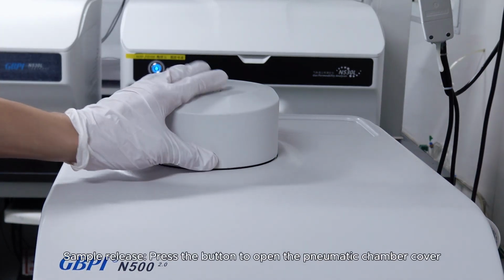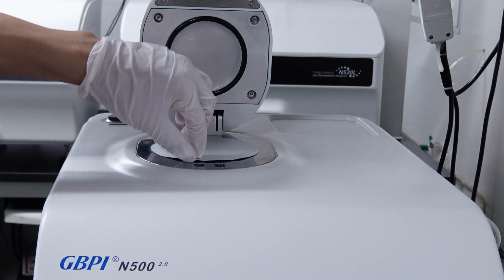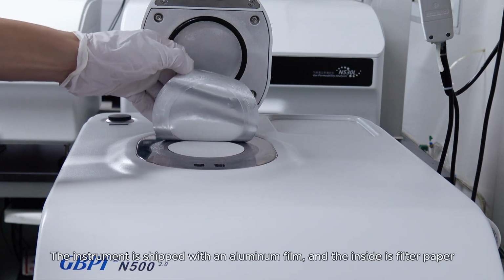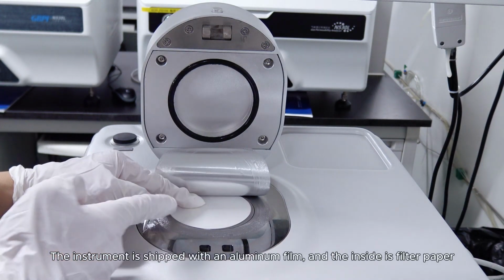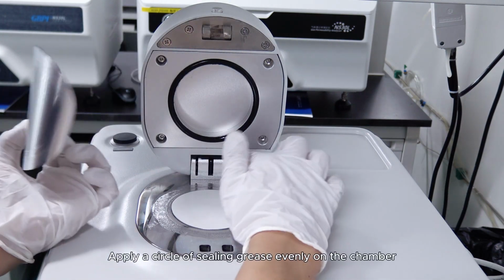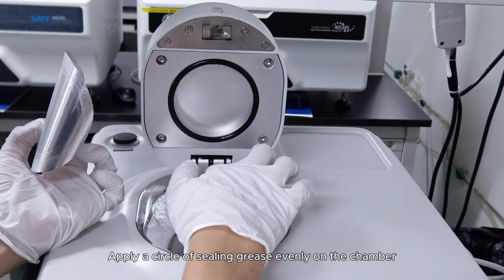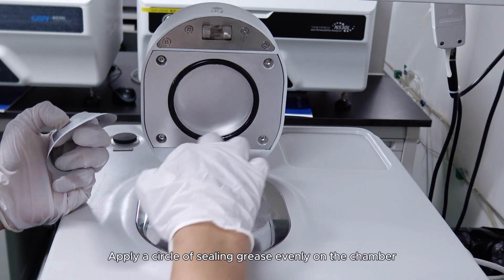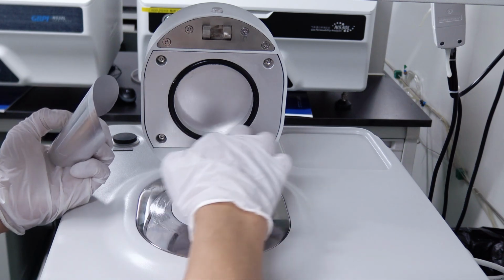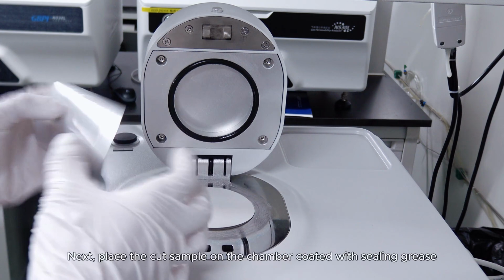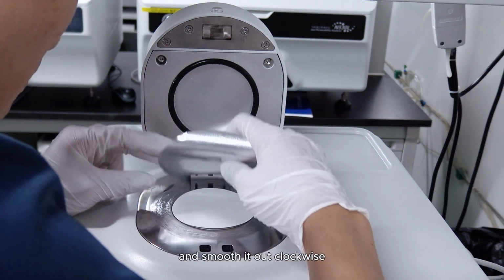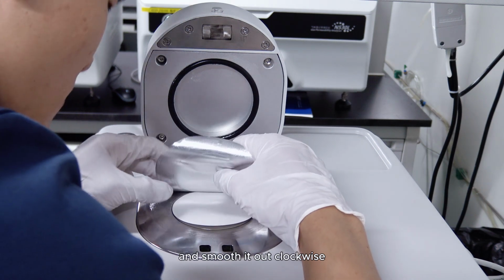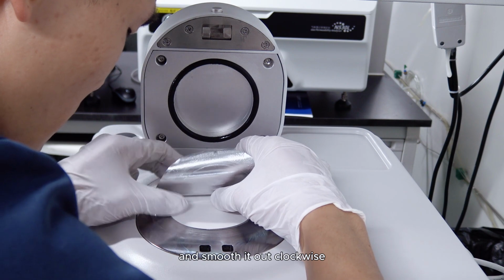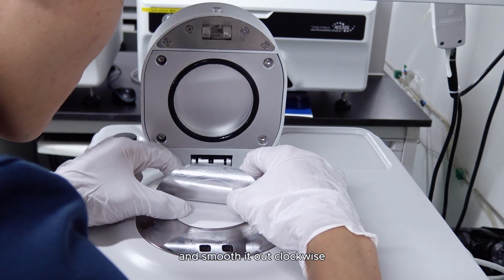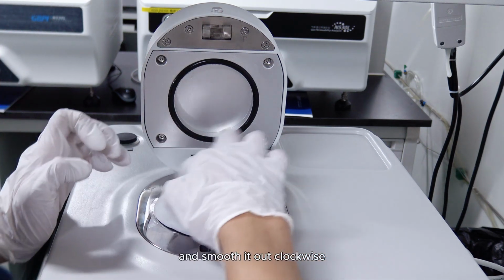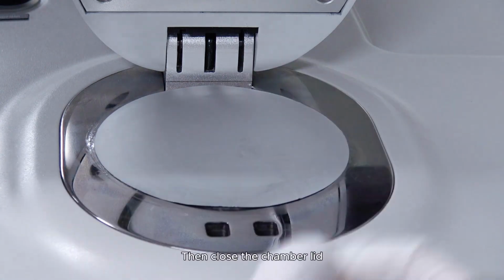Sample release. Press the button to open the pneumatic chamber cover. The instrument is shipped with an aluminum film, and the inside is filter paper. Apply a circle of sealing grease evenly on the chamber. Next, place the cut sample on the chamber coated with sealing grease and smooth it out clockwise. Then close the chamber lid.